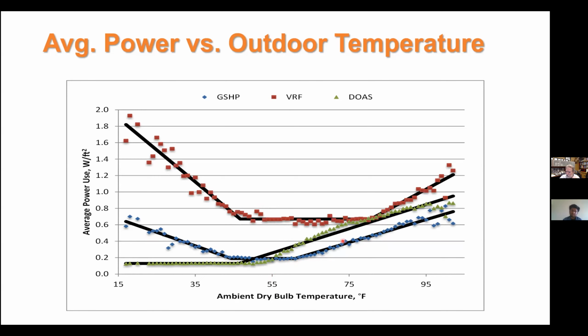And then as we get into the air conditioning season, we see the energy usage go up for both the VRF and the ground source heat pump system, as we'd expect with more cooling loads, and not quite as much difference there. Finally, the green is the DOAS system, where you can see that when it's cold there are no vapor compression cycles running. It's just recovering heat, so its usage is pretty constant. And then as it starts to get warmer, the cooling units start to come on, right? So it provides a certain amount of the cooling that way.